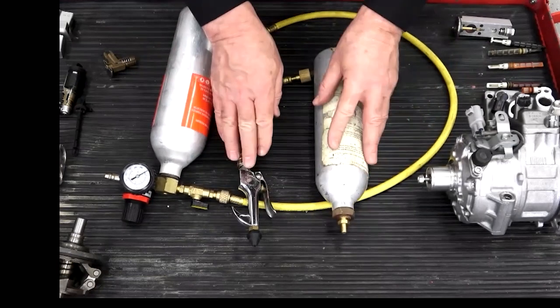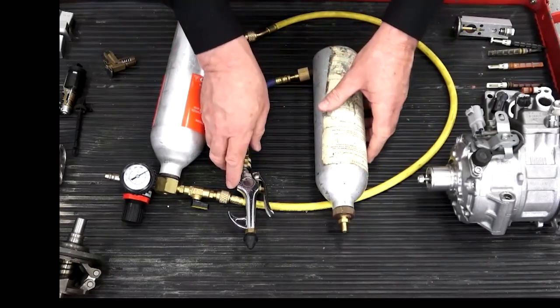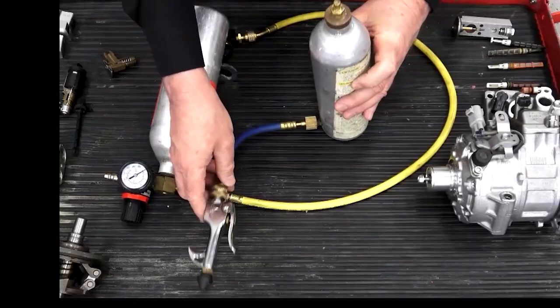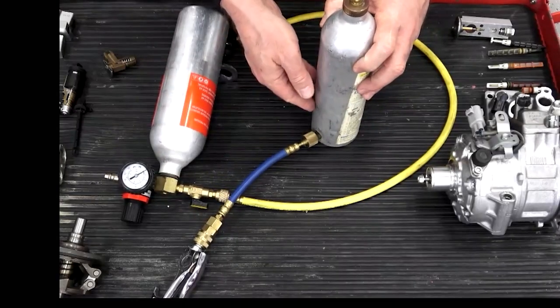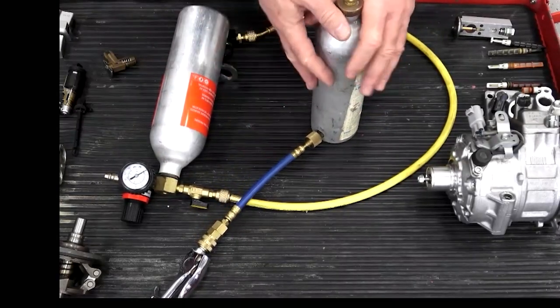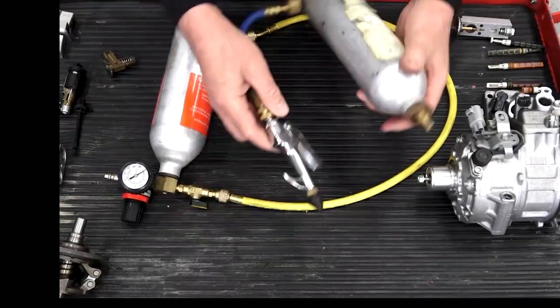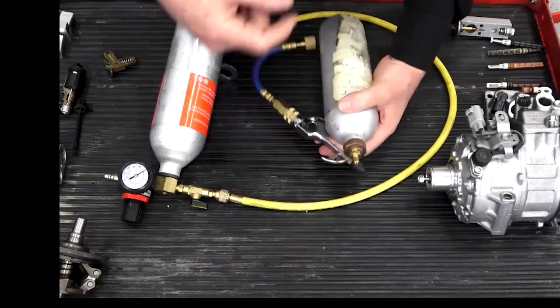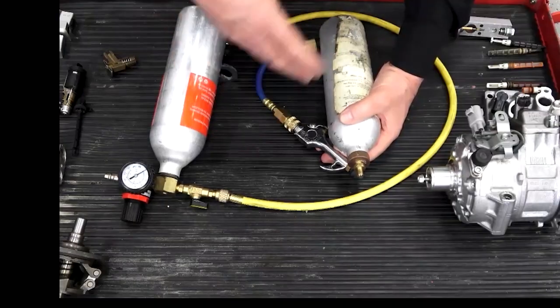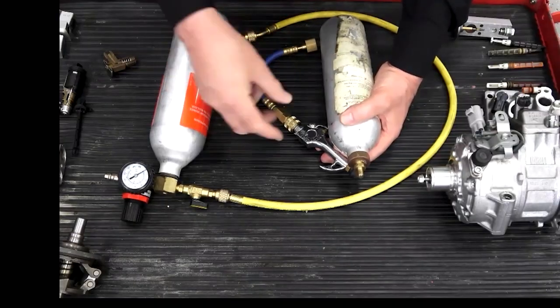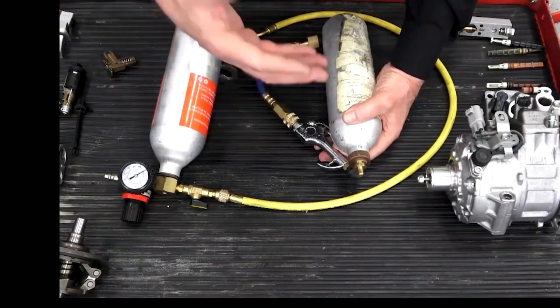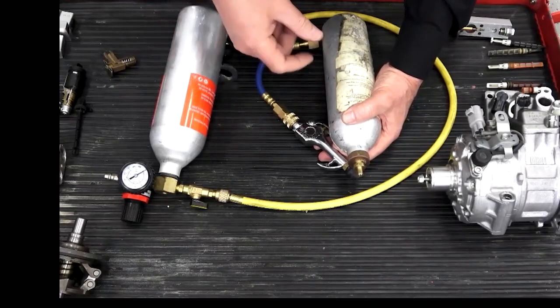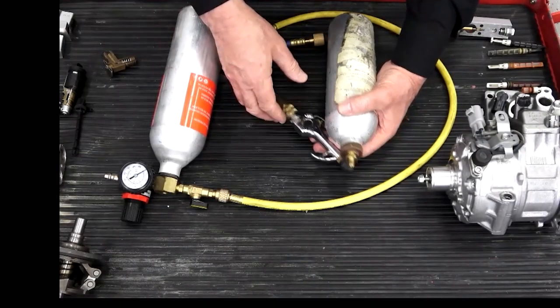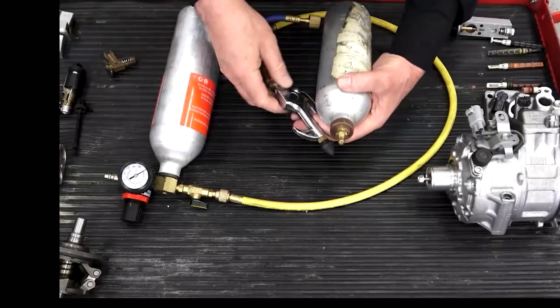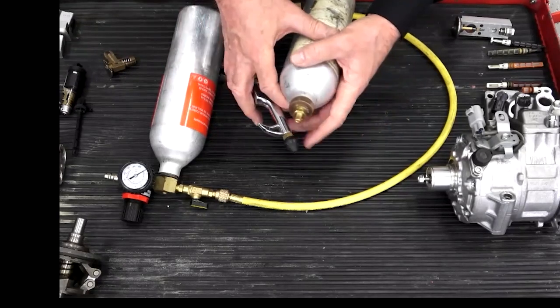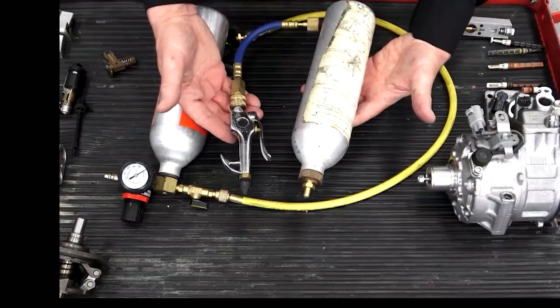I often say a bad flush is worse than no flush at all. Meaning, if I use a tool like this, the air is going to expand, drive some of the solvent out, then it runs out of oomph. The pressure drops rapidly, and all the solvent drops out inside the evaporator. Now you've got a dirty soup of abrasive metal particulates and dirty oil in the bottom of the evaporator, 2, 3, 4, 5 ounces. And if you put the system back together, when you charge it up, that dirty soup gets pushed out of the evaporator, and it tears the compressor apart in record time.